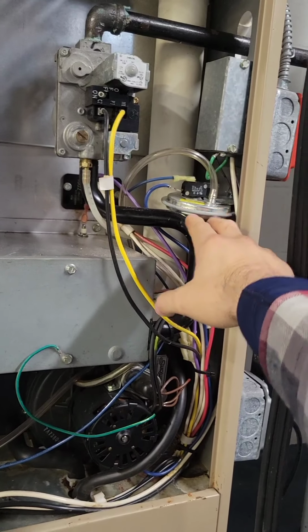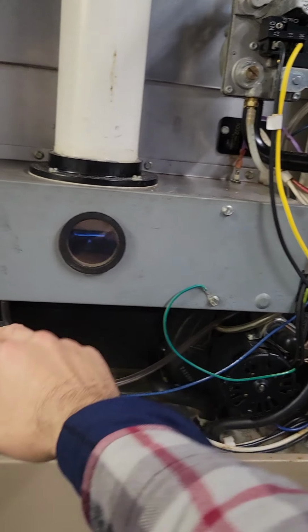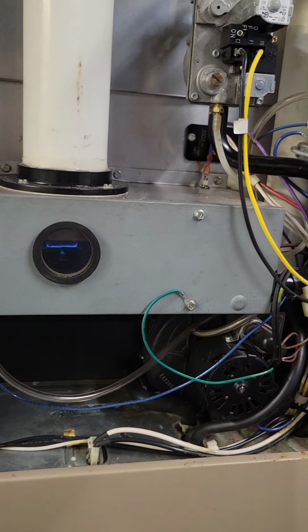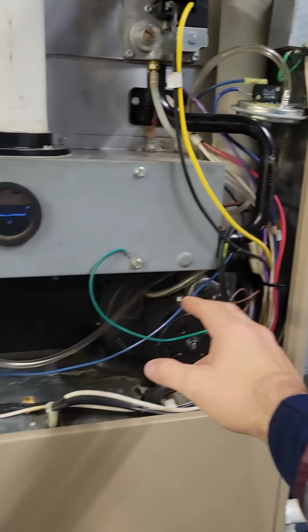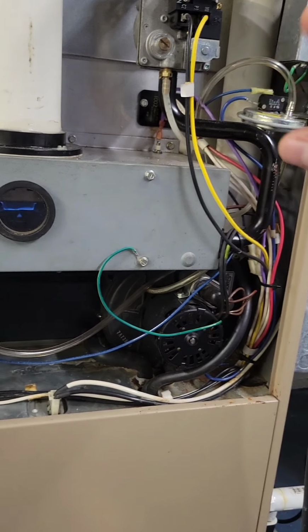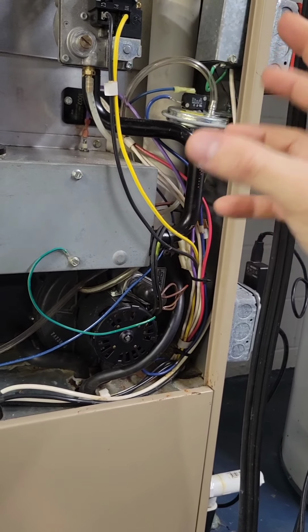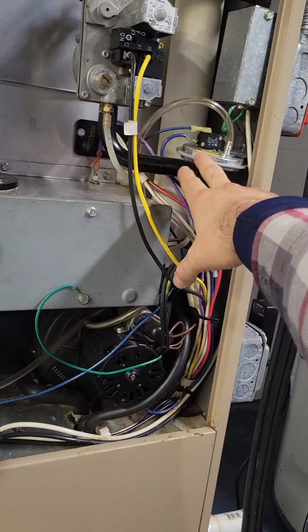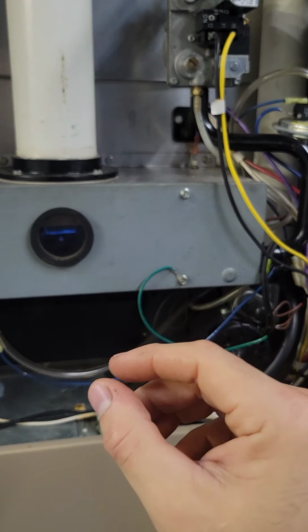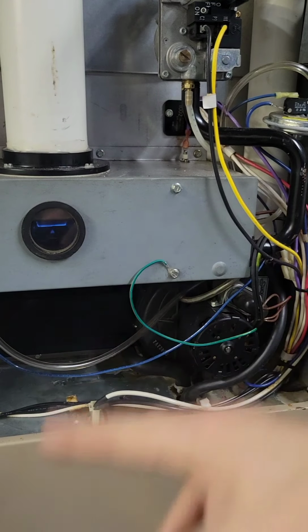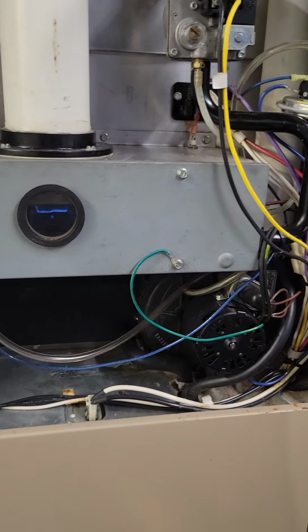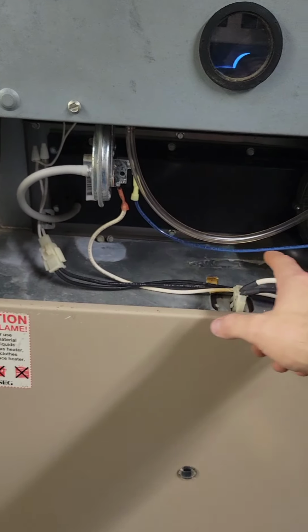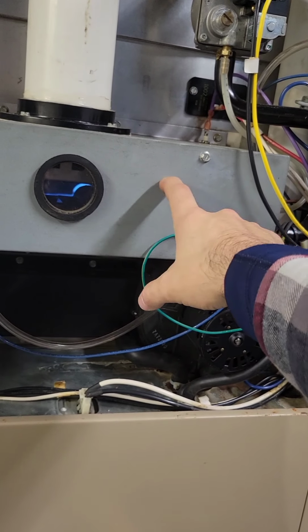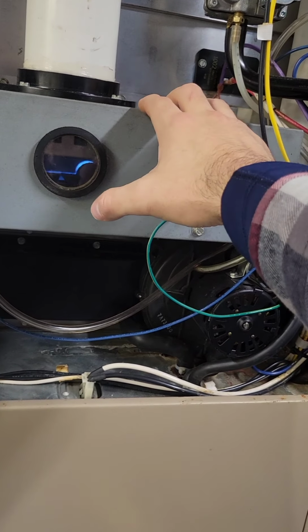You have your pressure switches, which help determine what exactly is going on with the draft. And if the inducer motor wasn't running, you'll get a pressure switch error code, or those guys won't close. They have a diaphragm inside, and they open and close based on suction and air pressure, right? So it'll be a typically normally open contact, it'll close. And then if you have a high efficiency furnace or 90% furnace, you'll typically find two pressure switches, positive and negative pressure switches. And you can see that this particular switch is actually hooked up to the chamber, to make sure that obviously we have enough combustion air and things of that nature.